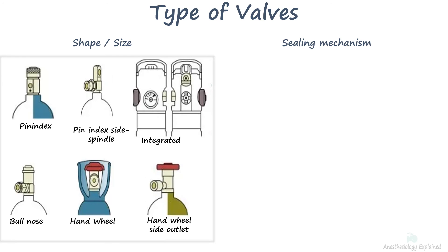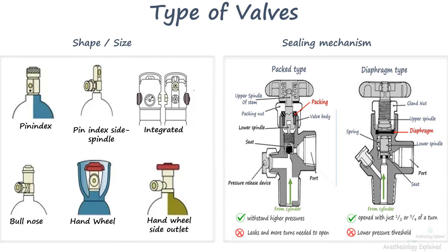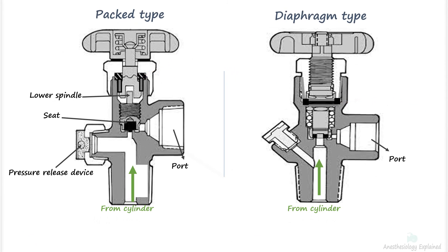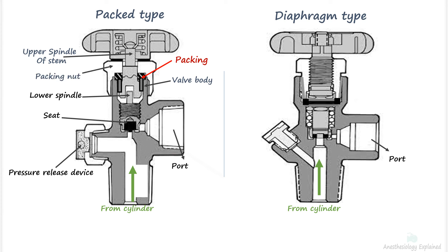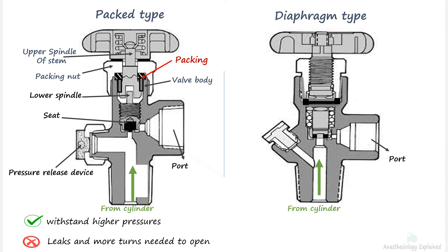Integrated valves have built-in regulators. Based on the sealing mechanism, valves are either packed or diaphragm type. In a packed valve, the stem is sealed by resilient packing such as Teflon. These valves utilize compressed packing to create a seal around the valve spindle and body, and the packing nut is tightened to compress the packing against the spindle. The primary advantage of a packed valve is its ability to withstand higher pressures; however, over time the packing may wear out and begin to leak, and these valves typically require 2 or 3 turns to fully open.